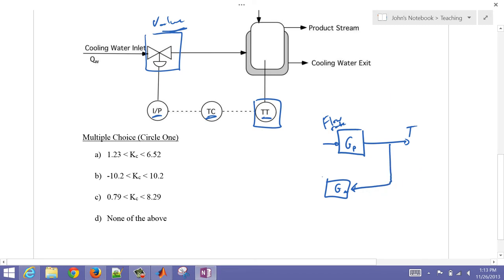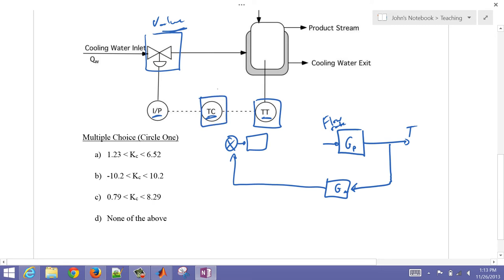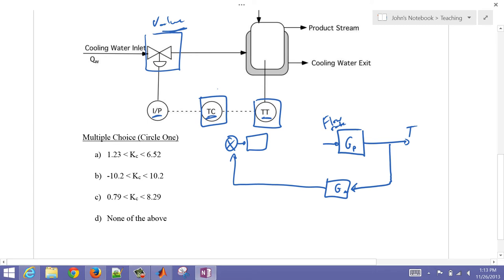That represents the temperature transmitter — that's the measurement. Then I'm going to have a controller. We're going to do a stability analysis. We can really only do a stability analysis with either a PI or a P-only controller. Most people just do it with a P-only controller to get an approximate gain — the upper and lower limits. So this is just going to be a Kc value for our controller.